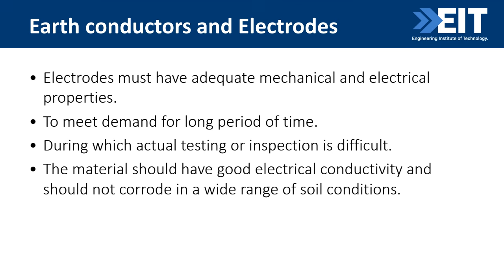So basically what we'll do with an earth is you can have a vertical rod that goes into the ground, and typically we would like a maximum of 1 ohm, but preferably 0 ohms to ground. One of the biggest challenges with earth conductors is trying to get the resistance as low as possible. Pete made a really good point: sandy areas are more difficult to achieve a decent earth compared to wet soil. So it's a whole area of design, really important.